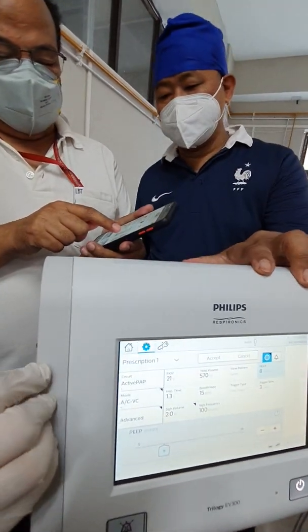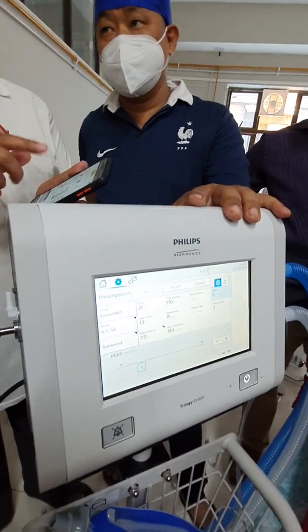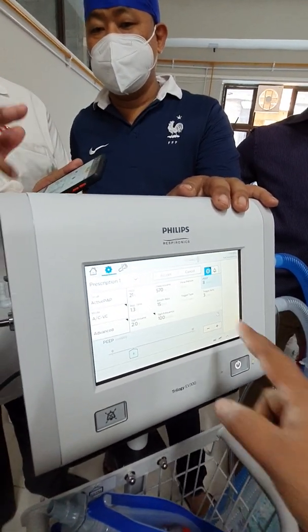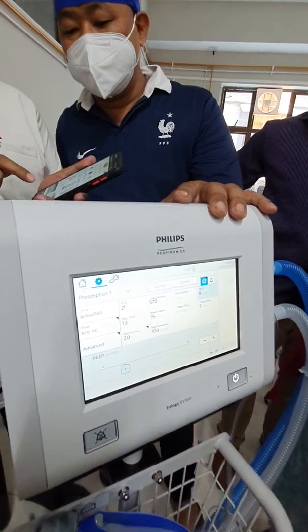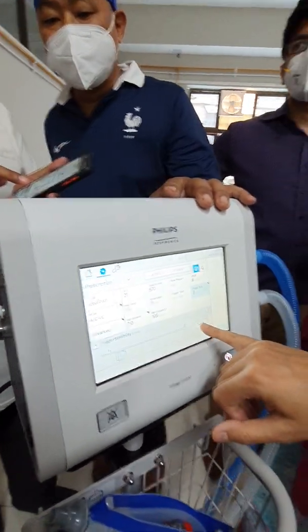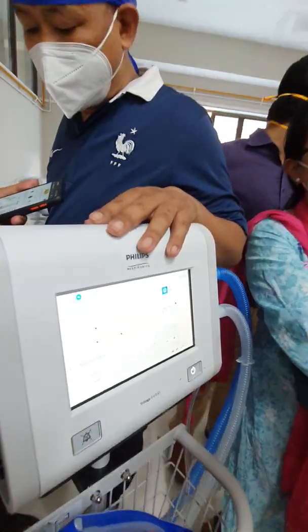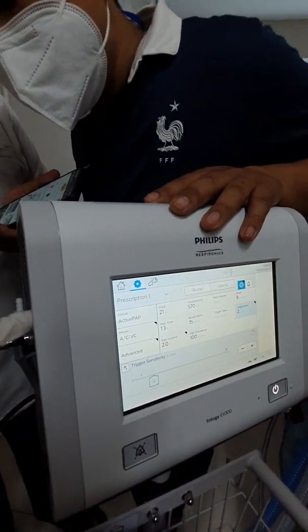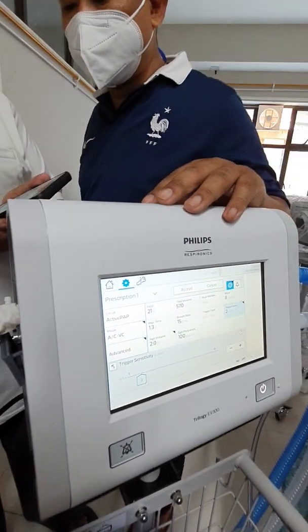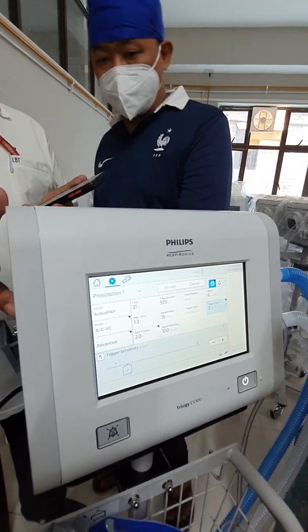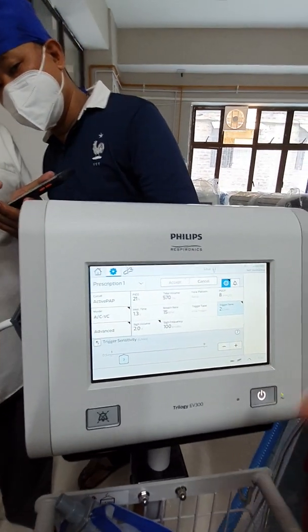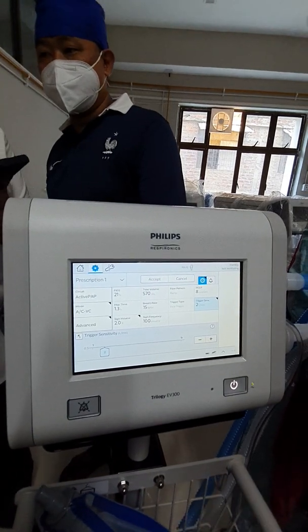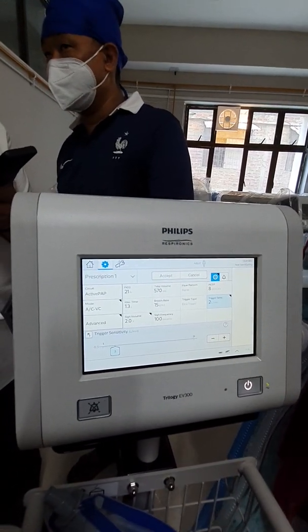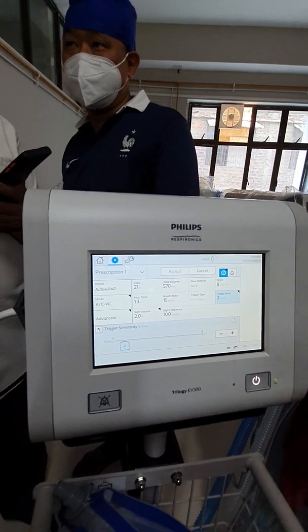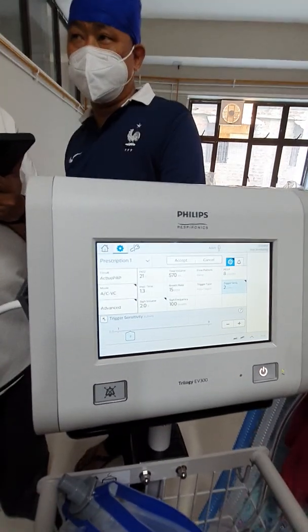If we purchase this thing, then it can be connected, or we need to buy the module. The module is inside; we have purchased it. We will give you the list of which trigger will connect, because this is USB. It has to be as per the software, then it calculates automatically. The trigger should be one or two, only applying the airway adapter and the cable. If it is a higher trigger, the patient will not be able to trigger the breath, so you have to set the trigger at a lower pressure. Don't raise the trigger above that.